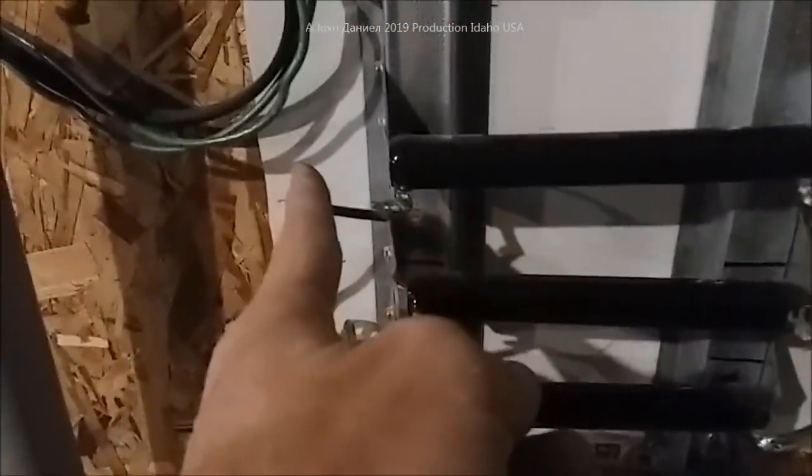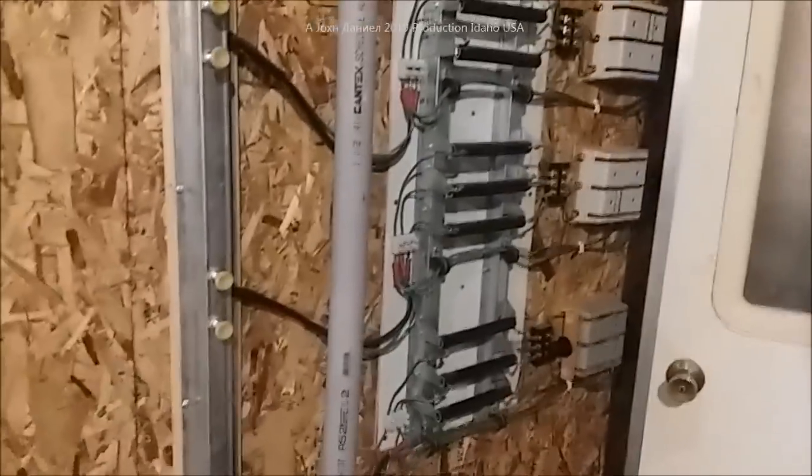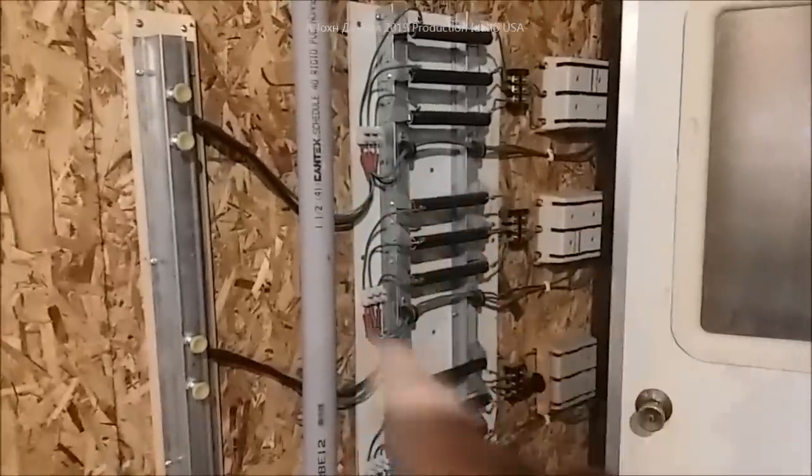The brake switches are just taking two leads — if you pull one it connects them direct, and it connects them direct back here too. Don't use these brakes unless you absolutely have no choice — meaning your building is in danger otherwise. Any toggle switch with just a brake/run open position is dumb — don't do it. These turbines produce a massive amount of power and we have to burn off power all the time. I'm going to show you a schematic of this diversion braking control system.